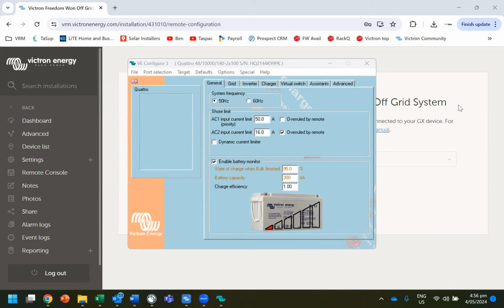In reality, that's probably going to be higher than 95%. Now, just so you know, any battery settings that you put into this inverter are actually not going to be used, because the battery controls all the charging and discharging settings. The only settings that will be used are the low voltage cutoff and state of charge shutdown, if you want to use that.